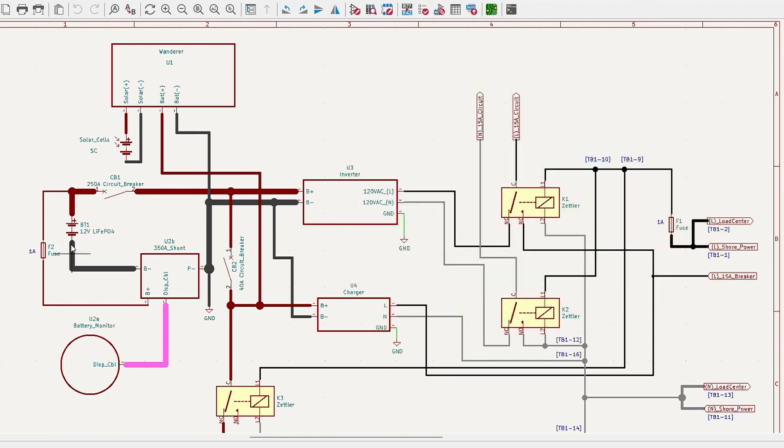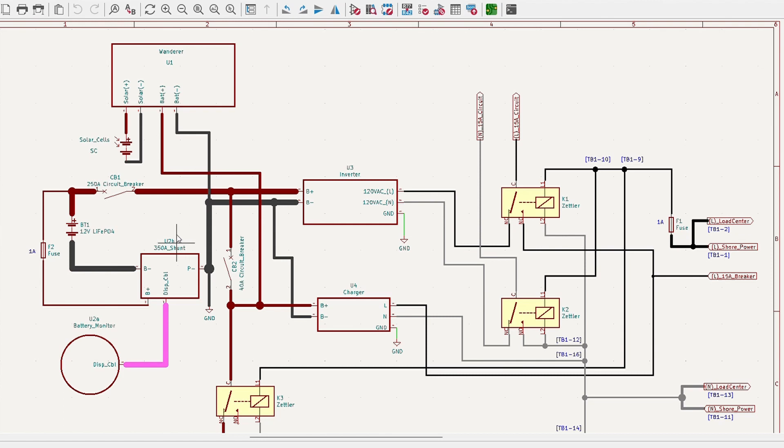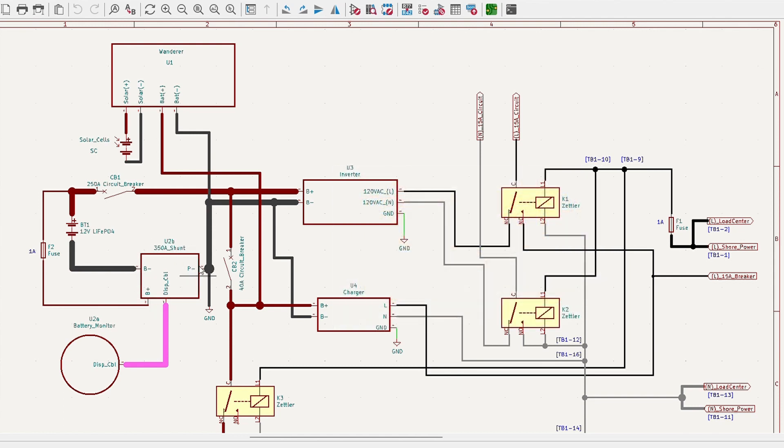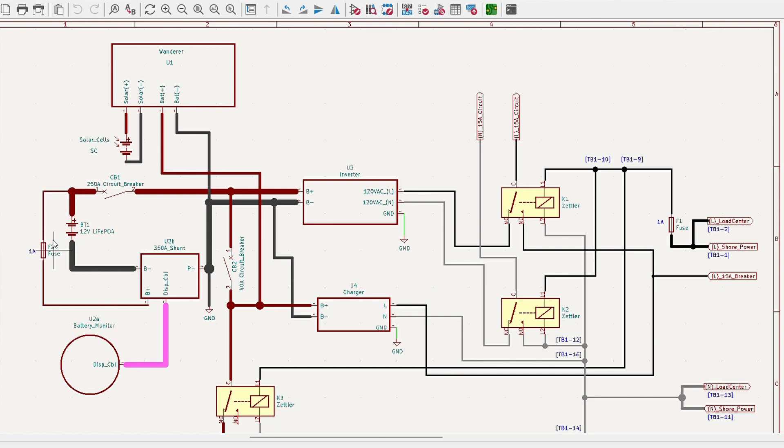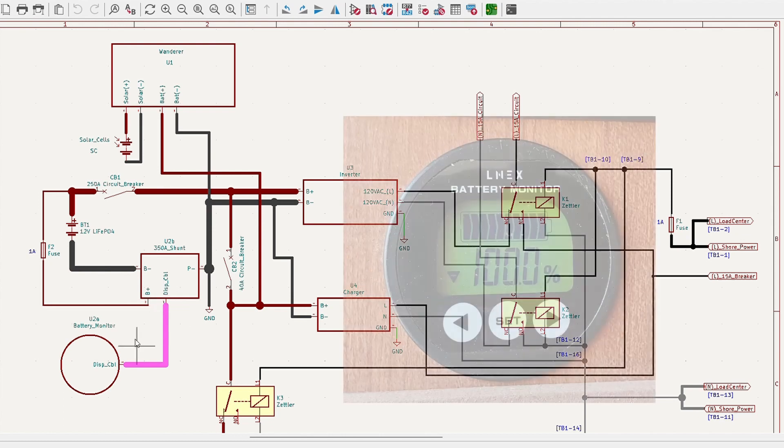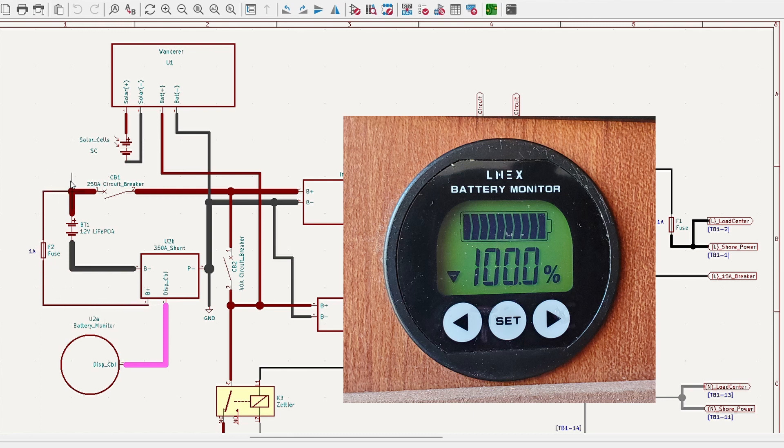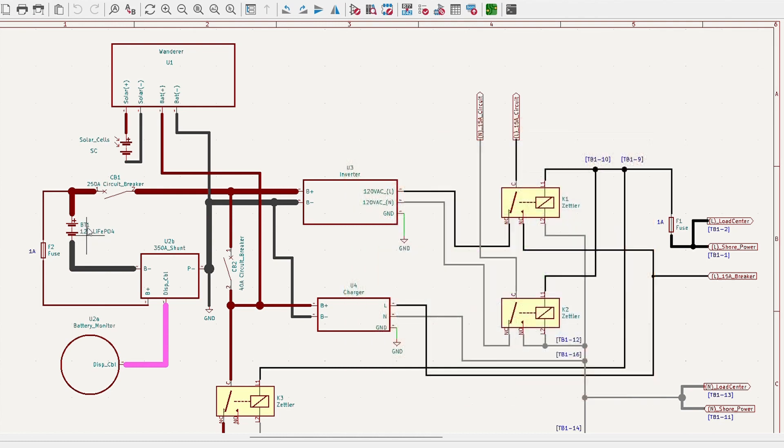Looking down below this dark line here is our negative terminal, and it eventually connects to ground, but it goes through a 350-amp shunt as part of the battery monitor system. This shunt determines any current flow going through the system to determine whether the battery is charging or discharging. You'll also notice from the positive terminal, there is a fuse, F2, which is a 1-amp fuse that also connects to that shunt. This provides power for the battery monitor and also allows the battery monitor to check the voltage at the BT1 battery.